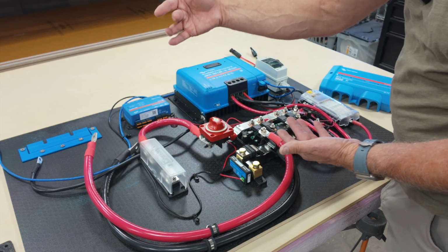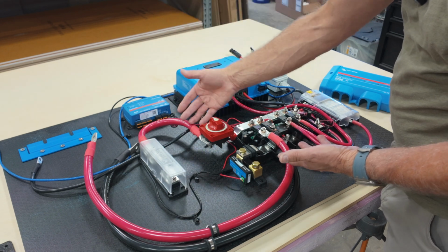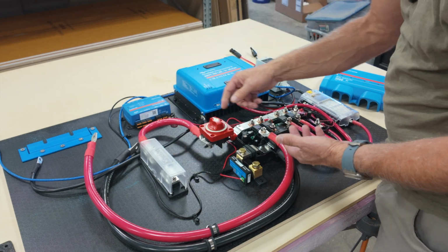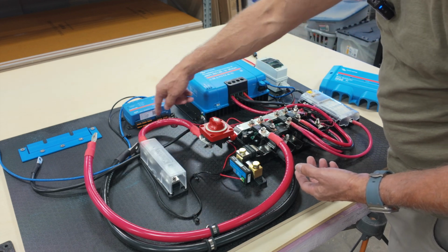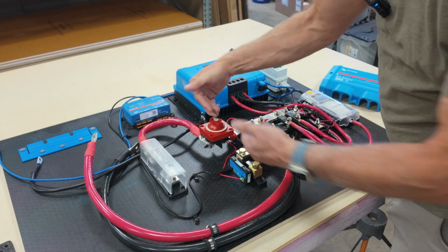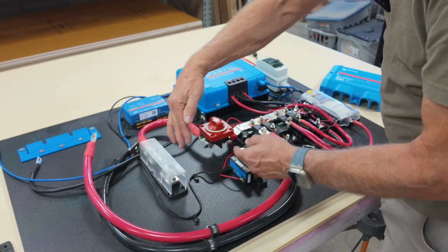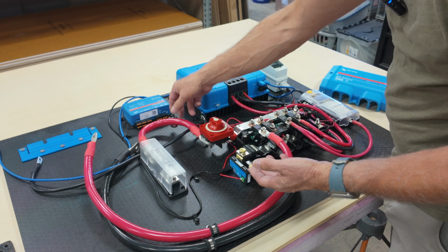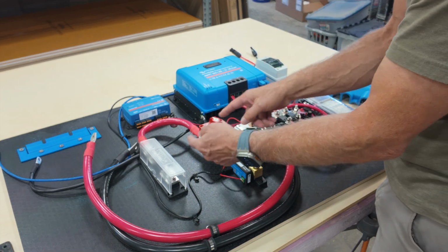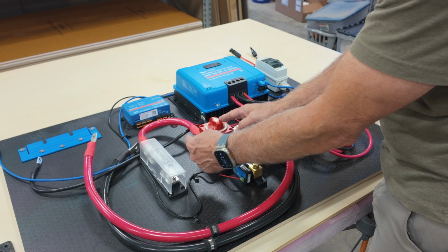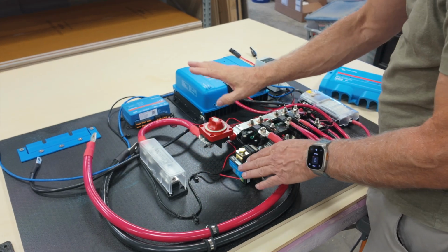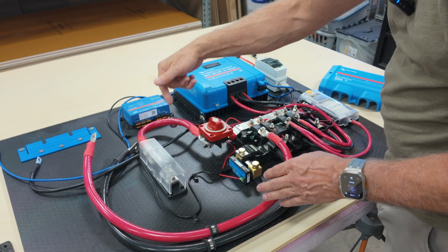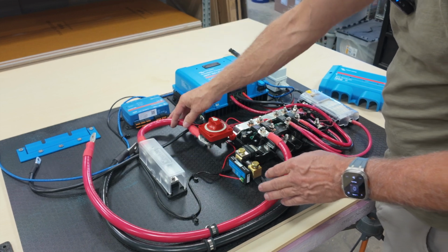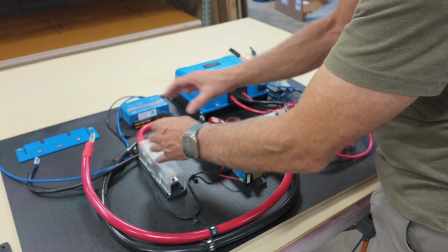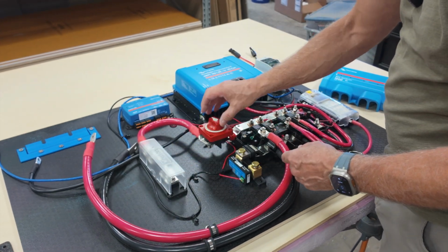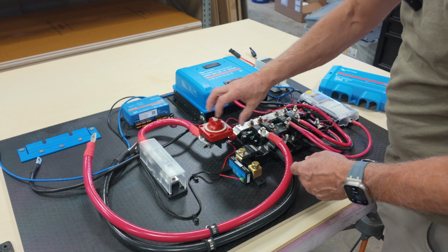If you don't do that, then you have to use battery cable. In this case, we have a 12-volt system with a 3,000 watt inverter, so we've got 4-aught cable. Even this short one, about 8 or 10 inches long, is hard to work with—you need some space to get it to curl. You can't make very tight turns with this big battery cable. So if you're attaching your switch and running a battery cable to it, it costs more money because you've got to have the lugs, crimp them, shrink them—it takes more time, and you need space between all of these different things. By attaching the switch directly to the bus bar, we eliminate that.